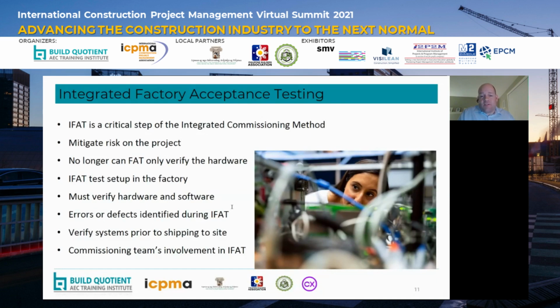If that instead is deferred all until site, where you want to integrate the hardware and software together once the equipment arrives at site, then any errors that are found at that time are a critical delay to the commissioning critical path sequence, and that can get quite expensive. We'll talk about that in a second. You definitely want to advance and de-risk the project by looking at all those items during your integrated factory acceptance test.